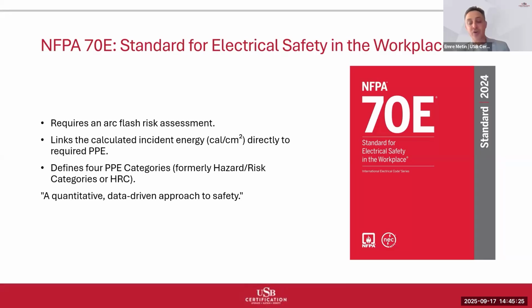Category 4, minimum 40 calorie per centimeter square arc rating. But here's a critical point. These are minimum requirements. If your analysis shows 15 calorie per centimeter square incident energy, category 2 PPE is inadequate. You need garments rated for at least 15 calorie per centimeter square.